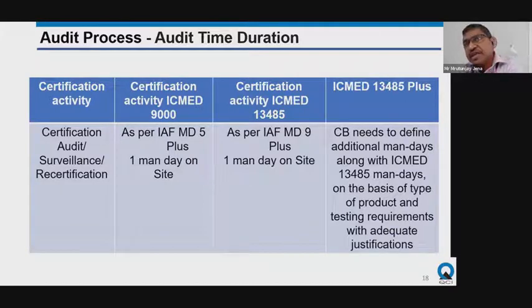These man-days will be spent by the certification body, as decided by the certification body. The certification body has to develop a system for how they calculate the man-days to be spent at the manufacturer end, at stage 1 or stage 2 level, with justification for how that man-day differs based on multi-site locations, multi products at different locations, and whether it is a risky product such as implantable, active implantable, non-active implantable, or non-implantable.